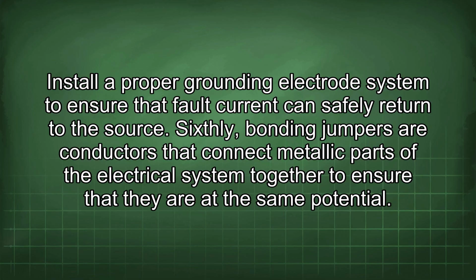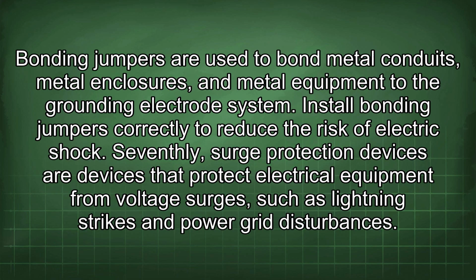Sixthly, bonding jumpers are conductors that connect metallic parts of the electrical system together to ensure that they are at the same potential. Bonding jumpers are used to bond metal conduits, metal enclosures, and metal equipment to the grounding electrode system. Install bonding jumpers correctly to reduce the risk of electric shock.